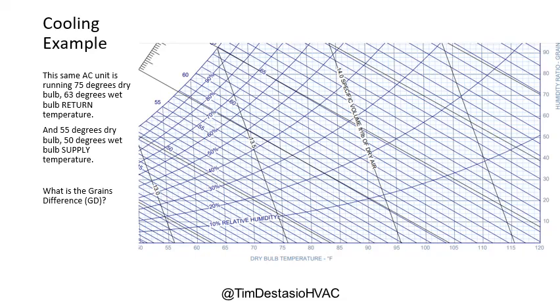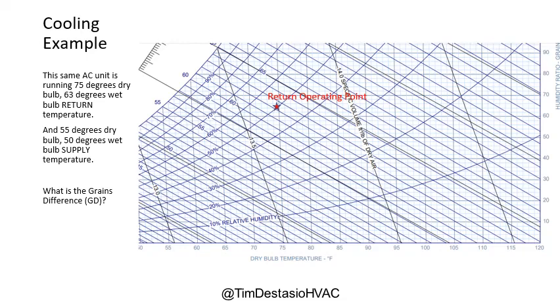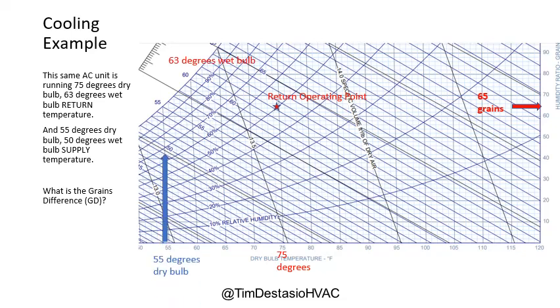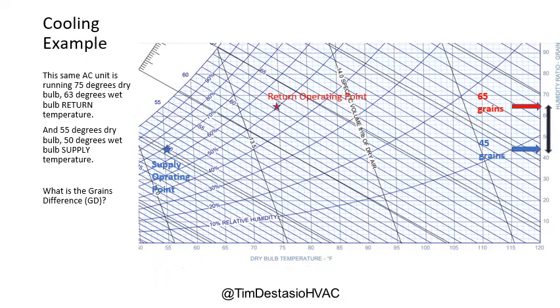The same air conditioning unit we've been discussing is running at 75°F dry bulb and 63°F wet bulb on the return. Plotting those on the psychrometric chart and carrying the operating point across to the right, we arrive at 65 grains of moisture on the return. On the supply side, we have 55°F dry bulb and 50°F wet bulb. Carrying that operating point to the right gives us 45 grains of moisture. The grains difference is 65 minus 45, which equals 20 grains — that's the value we plug into the latent heat formula.